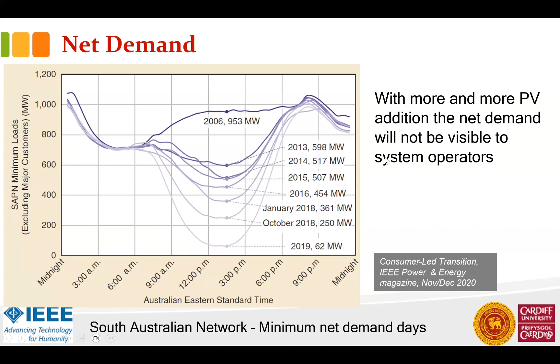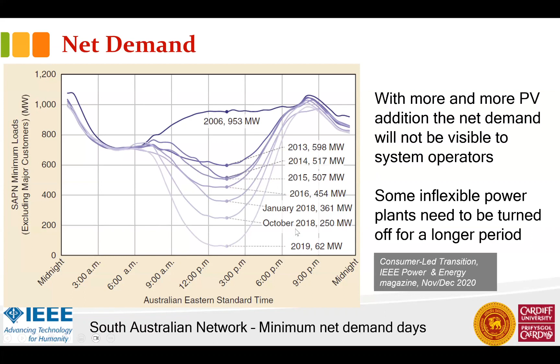The other issue is, running a system at that kind of net demand, you need to switch off some of the plants. You can easily switch off a hydropower plant or a single cycle power plant, but switching off a coal power plant is a nightmare. So you can't switch it off. What happens is you reduce their load to zero, so they're still running, still spinning, but not producing any power.